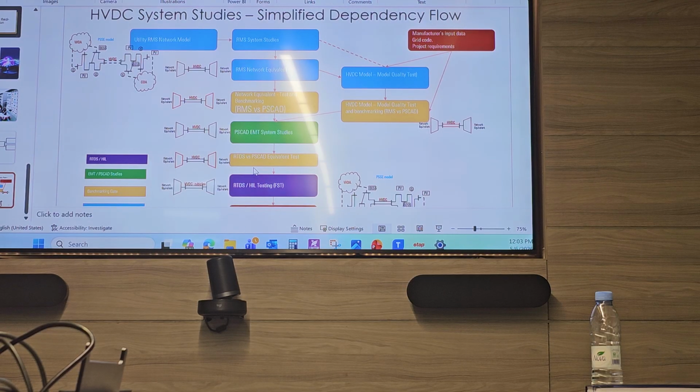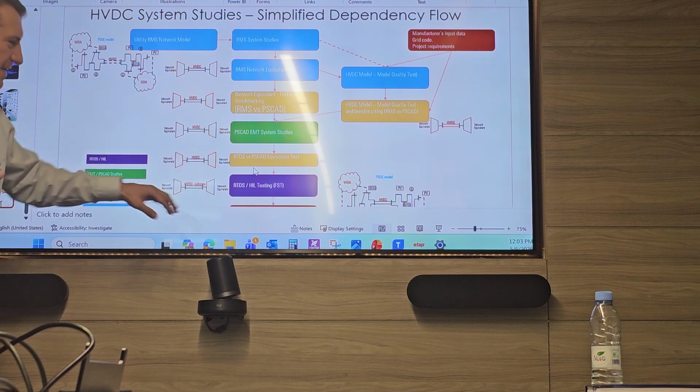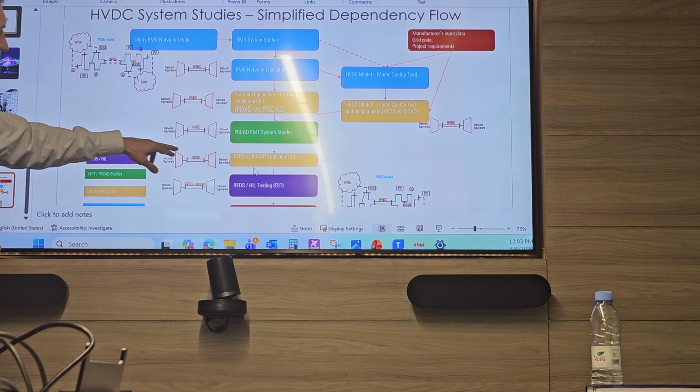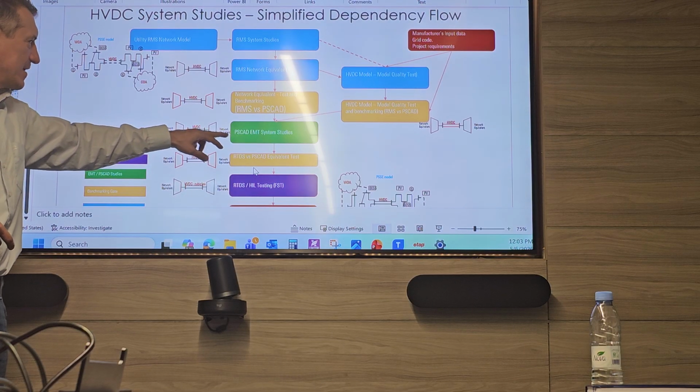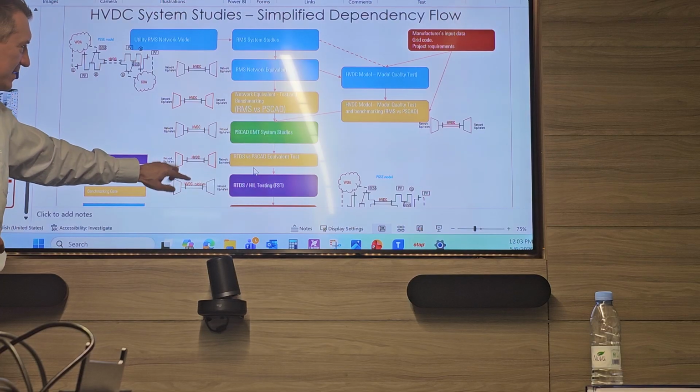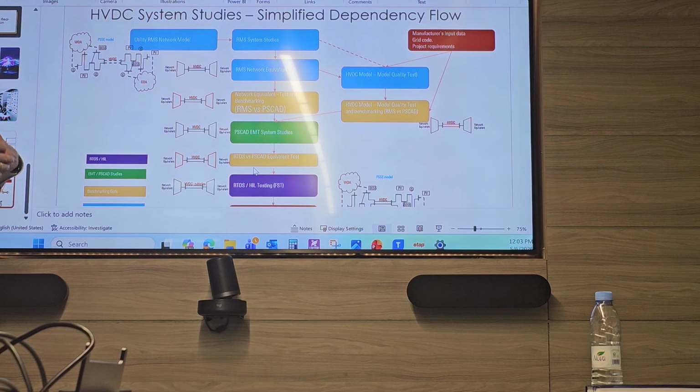So this is why, and finally, once this test is done, they will have this RTDS model in the laboratory. Before they do any test in future in RTDS, they will do it in a PSCAD model, which again is equivalent, and these models are aligned, practically the same, and the same will be reflected here. So any change in tuning in the real cubicles will be checked and reflected in the system. And this is how you could monitor what's going on.